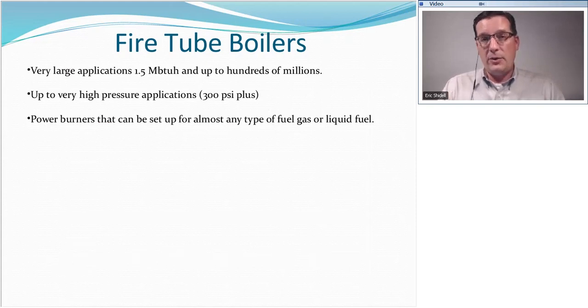They're a different animal. Even though the same essential boiler can be used in low pressure applications or in high pressure applications, when it's high pressure, it is a very, very dangerous animal. And we're talking about very extreme amounts of energy being circulated through this high pressure water system. High pressure water can exist as water and not steam at very, very high temperatures into the hundreds of degrees Fahrenheit. Now, normally when water boils in a pot on your stove at home, 212 degrees is the boiling temperature of water. When we get that water under pressure, especially very high pressure, we can have water temperatures of 300, 400, or more degrees Fahrenheit and still be water.